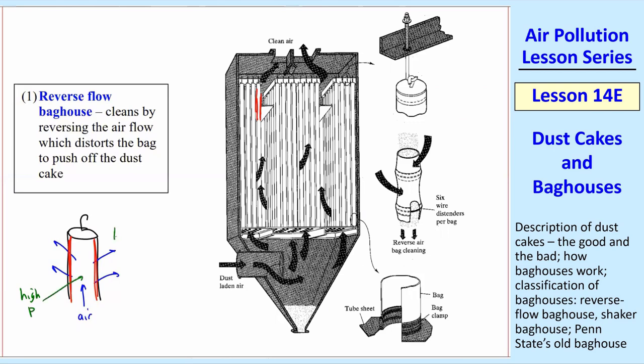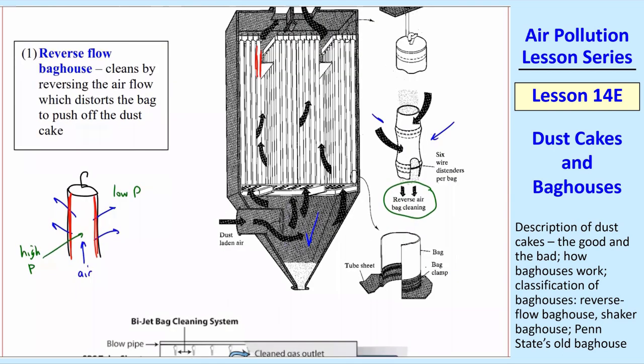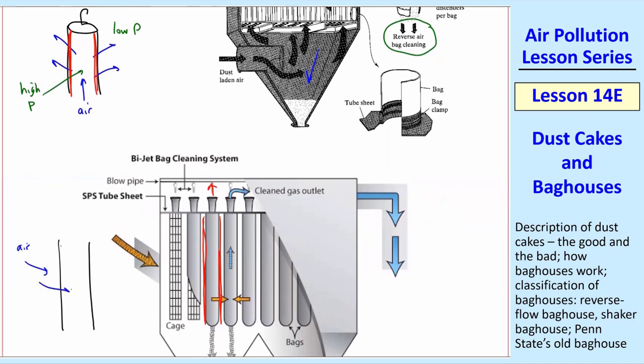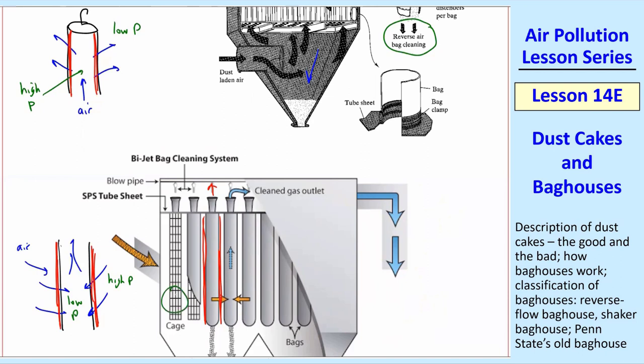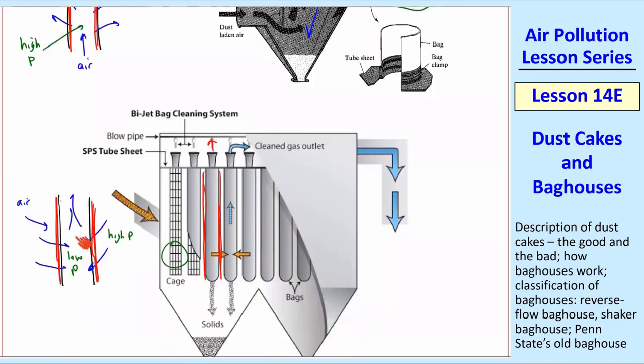For this case, there's high pressure inside and lower pressure outside. What a reverse flow bag house does is reverse this flow, so the air goes the opposite way — it comes in from the outside to the inside, which sort of collapses the bag a little bit and dislodges the dust cake, which then falls down into a hopper. That's a reverse flow bag house. In the other configuration, the air comes to the outside of the bags and the clean air comes out from the inside, so the dust cake builds up on the outside. There's a wire mesh cage that keeps the bag from collapsing, because the high pressure is on the outside and the low pressure is on the inside. That's why you need the cage so the bags don't collapse. In the first type, the bags are stiff enough that they just get filled with air and don't collapse on their own.